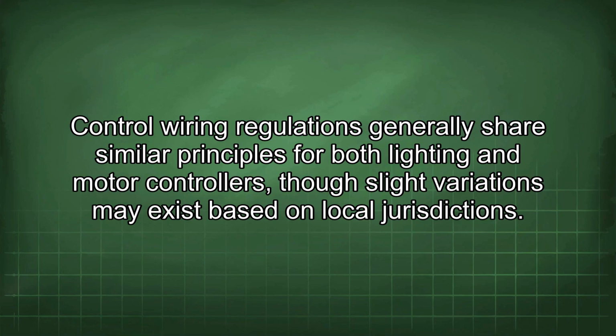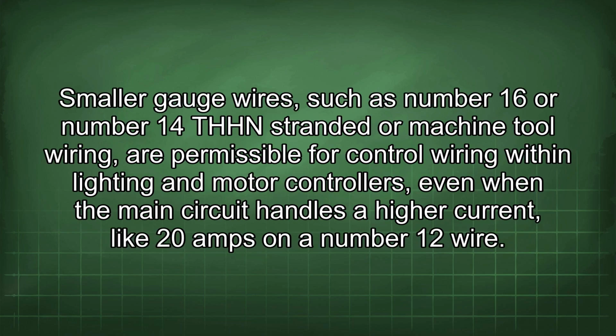Control wiring regulations generally share similar principles for both lighting and motor controllers, though slight variations may exist based on local jurisdictions. Smaller gauge wires, such as number 16 or number 14 THHN stranded or machine tool wiring, are permissible for control wiring within lighting and motor controllers, even when the main circuit handles a higher current, like 20 amps on a number 12 wire.